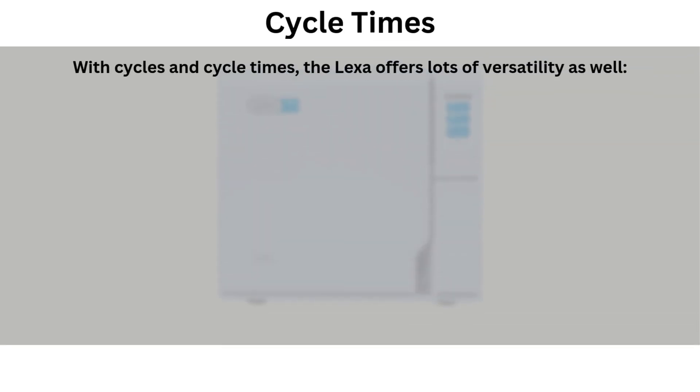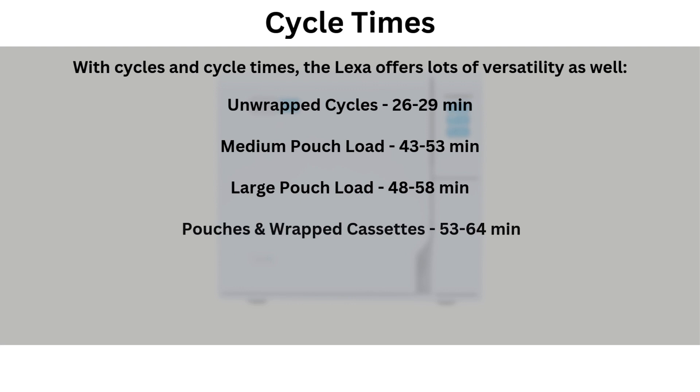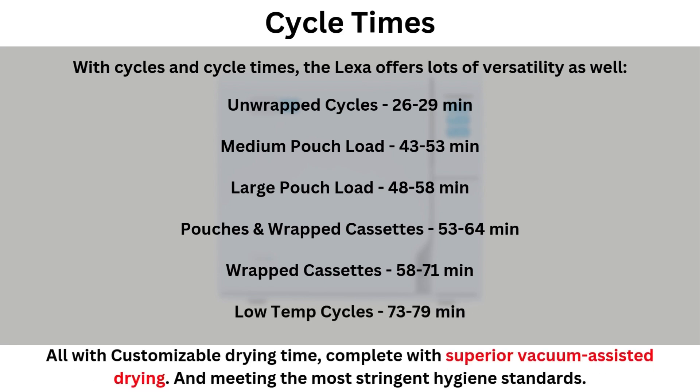With cycles, you get a lot of versatility too. Versatile sterilization program options with short cycle times like: unwrapped cycles at 26 to 29 minutes, medium pouch loads at 43 to 53 minutes, large pouch loads at 48 to 58 minutes, pouches and wrapped cassettes at 53 to 64 minutes, wrapped cassettes at 58 to 71 minutes, and low temp cycles at 73 to 79 minutes — all with customizable drying time, complete with superior vacuum-assisted drying, and meeting the most stringent hygiene standards.